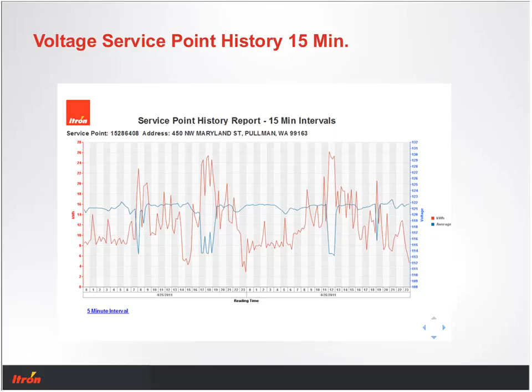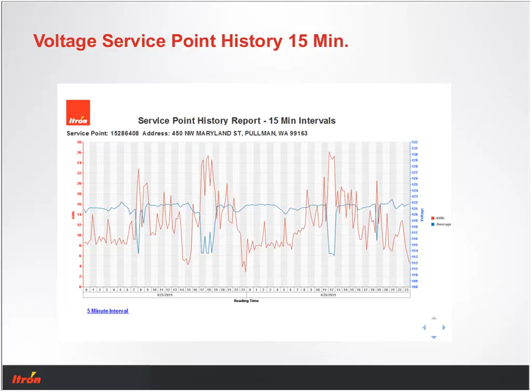So let's go in and get a little more granularity. Here's a 15-minute graph, and you can now see much better what's actually going on with respect to both load and voltage, and you get a more precise measure of the voltage and how long it was at that particular voltage. I can see a couple of places here where we have some issues with that voltage that occurred over more than just a single 15-minute interval. But you can also see that now I'm not averaged over 60 minutes, so I get a fairly good view of what's really going on.